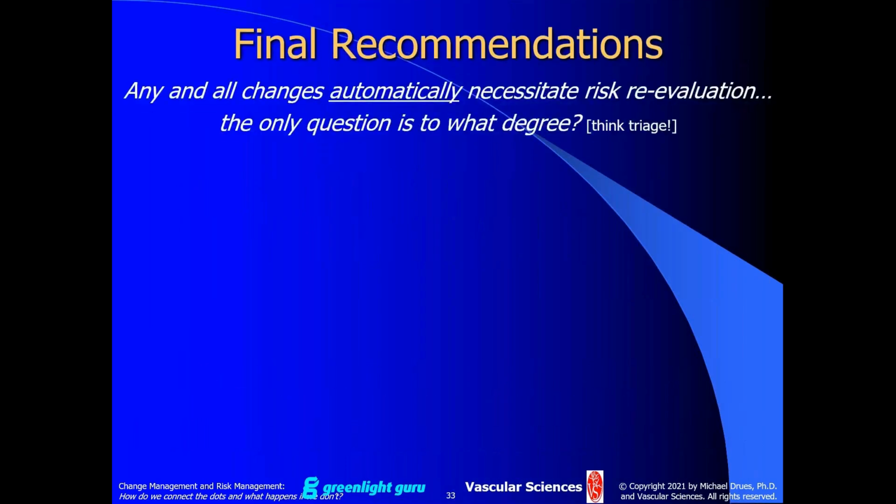So to wrap this up in terms of some final recommendations, any and all changes, this is a no-brainer for me, any and all changes should automatically necessitate a risk reevaluation. Whether it explicitly says that in the regulation somewhere or not really doesn't matter to me. Any and all changes should automatically necessitate a risk reevaluation. The only question, the only gray area, the only ambiguity, is to what degree. And as I talked about before, think triage. Not all changes should be treated the same.